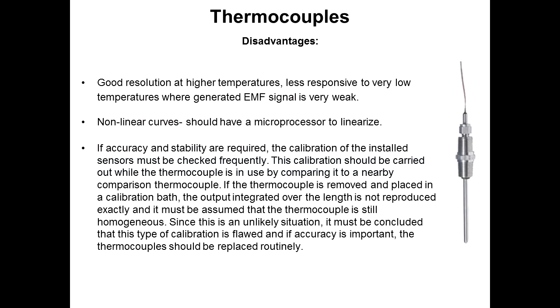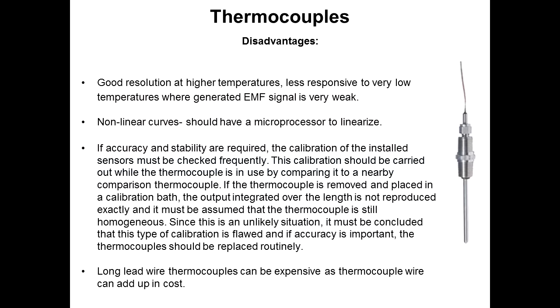If you pull them out and hook them up to a different set of wires, you won't have exactly the same situation. And long lead wire thermocouples can be expensive, as thermocouple wires will add up in cost. So for a lot of people, a transmitter is the best application there, where you're sending 4 to 20 over copper wire long distances rather than filling with thermocouple wire.